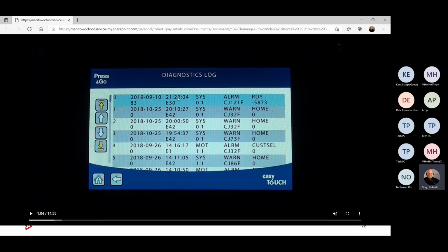Column 3 is your timestamp in military time, and underneath that is your error code or alarm code. Column 4 kind of dictates what system you're going to look into. So an E30 is in system 1. I don't know what E30 is off the top of my head; I would have to look at the chart. But I know it's in my system 1, which is your main power.